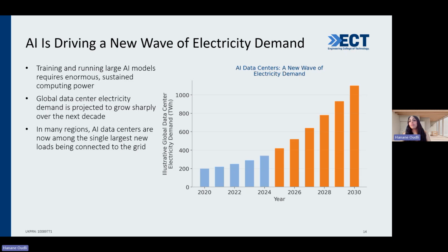The key point for power engineers is scale and concentration. A large data center campus can be a very substantial new load. And unlike many industrial loads, operators expect very high availability and continuity. So a utility fielding a large connection request has to look well beyond generation, transmission, and distribution capacity: voltage performance, short circuit levels, protection, dynamics, and contingencies. There is also an interaction with renewables. Adding large inverter-based generation and large concentrated digital load together means traditional planning assumptions may no longer hold. That's why AI data centers are a power system engineering topic, not just a data center one.